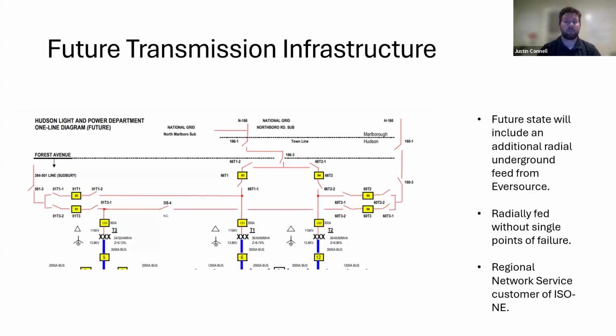Combine that with the fact that we'll be radially fed, where power can come from either direction, and with us building the 6-position ring bus, we have an incredible amount of redundancy, especially with an underground line coming from Eversource, a totally different utility, which should make our reliability that much stronger. On top of that, this new Eversource line is rated by engineering standards for 400 megawatts, almost 8 times more than Hudson's current peak demand. We can't use all of that right now because, going back to contingency risk, we always want to have an N+1, a backup.